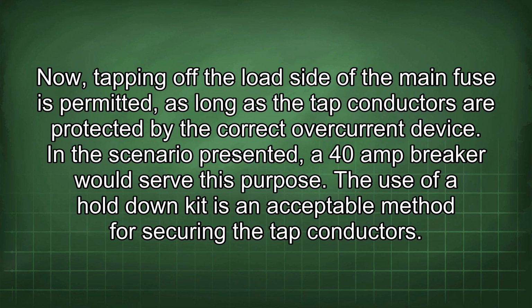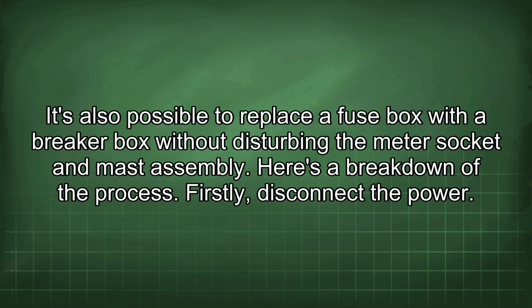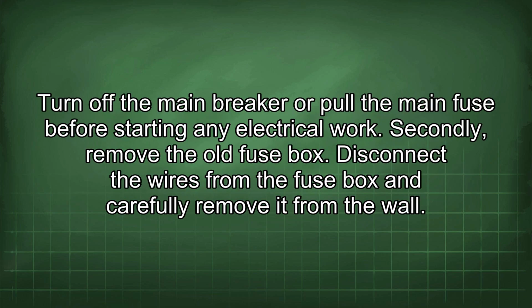The use of a hold-down kit is an acceptable method for securing the tap conductors. It's also possible to replace a fuse box with a breaker box without disturbing the meter socket and mast assembly. Here's a breakdown of the process. Firstly, disconnect the power. Turn off the main breaker or pull the main fuse before starting any electrical work. Secondly, remove the old fuse box. Disconnect the wires from the fuse box and carefully remove it from the wall.